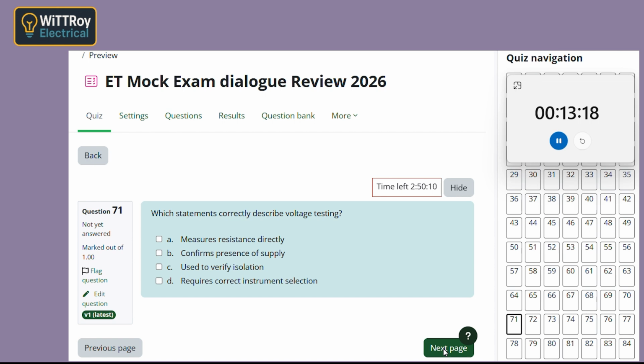Question 71. Which statements correctly describe voltage testing? Confirming supply and checking isolation? Yes, you're basically asking, is it live or not? So before and after isolation. Exactly. Before isolation, you confirm it's live. After isolation, you confirm it's dead. And you need the right instrument. Yep, and it doesn't measure resistance. That's a different test.